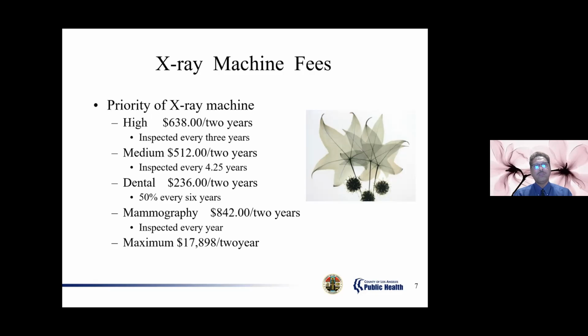And then we get to the high priority units. These are the ones used in the hospitals, the ones that you have probably operated. These are the diagnostic X-ray machines, the C-arms, all the special procedure C-arms, fluoros, radiation therapy units, and CT. Of course, MRI is not part of it, because MRI is not part of this field at all. We always get categorized with it, but we have no laws to enforce MRI. So CT is included, and with those types of machines, we inspect every 2.5 to 3 years approximately.